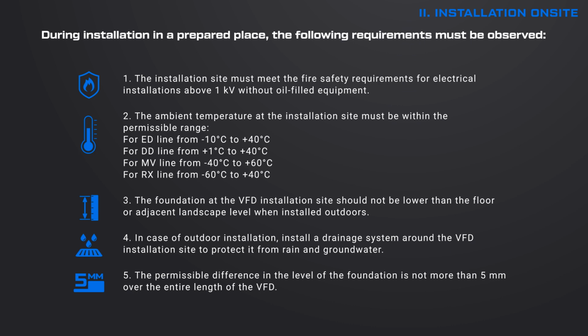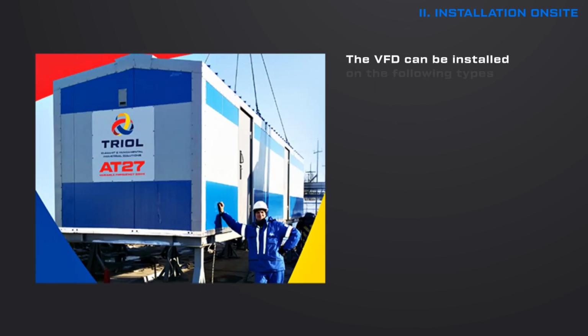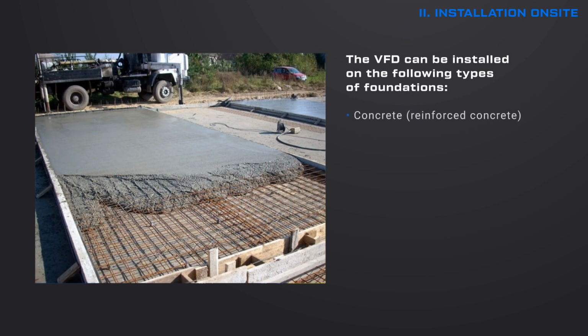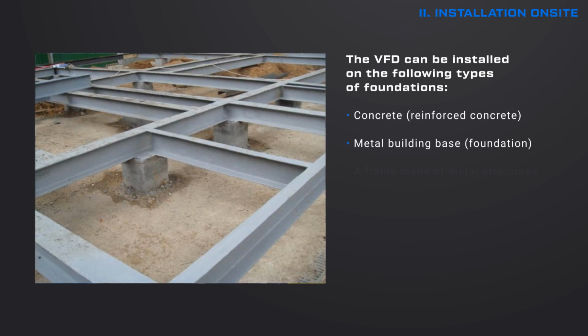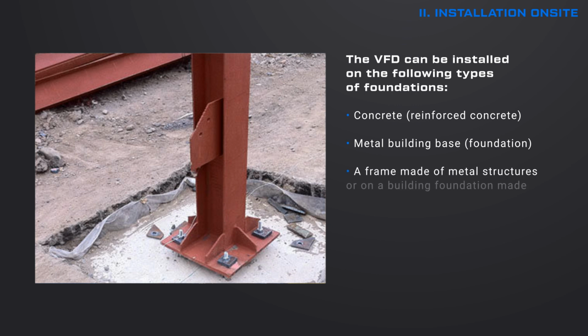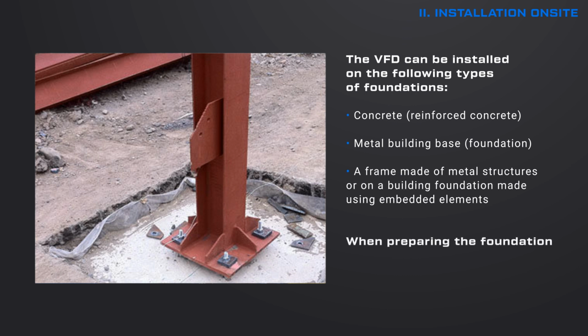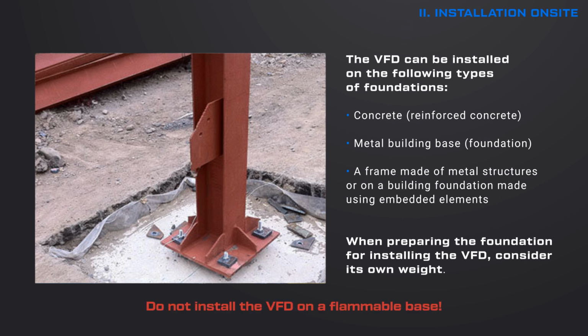length of the VFD. The VFD can be installed on the following types of foundations: concrete, reinforced concrete, metal building base, foundation, a frame made of metal structures, or on a building foundation made using embedded elements. When preparing the foundation for installing the VFD, consider its own weight. Do not install the VFD on a flammable base.